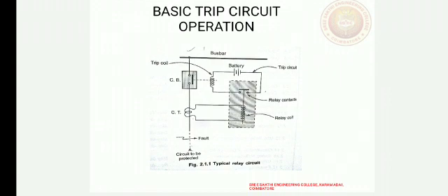A relay is a device which detects the fault and is responsible to energize the trip circuit of a circuit breaker. This isolates the faulty part from the rest of the system. If the fault occurs, then current through the line connected to A increases to a very high value. The current transformer senses this current. Accordingly, its secondary current increases, which is nothing but the current through the relay coil. Thus, the relay contacts get closed mechanically under the influence of high fault current.